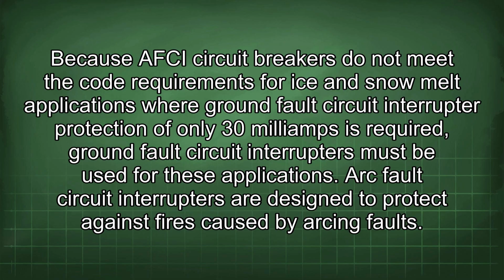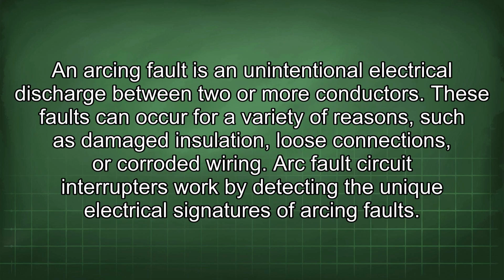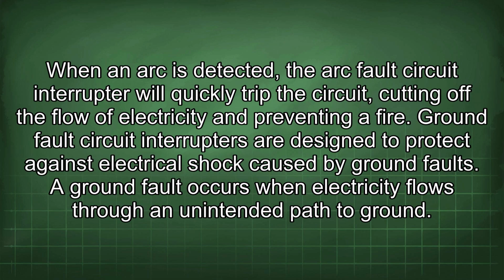Arc fault circuit interrupters are designed to protect against fires caused by arcing faults. An arcing fault is an unintentional electrical discharge between two or more conductors. These faults can occur for a variety of reasons such as damaged insulation, loose connections, or corroded wiring. Arc fault circuit interrupters work by detecting the unique electrical signatures of arcing faults. When an arc is detected, the arc fault circuit interrupter will quickly trip the circuit, cutting off the flow of electricity and preventing a fire.